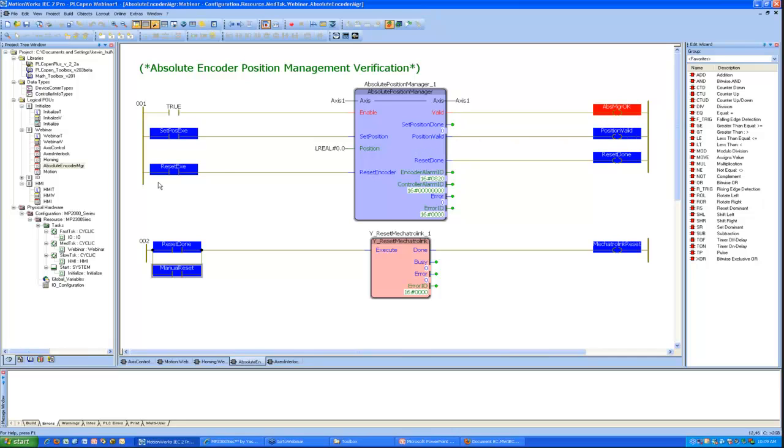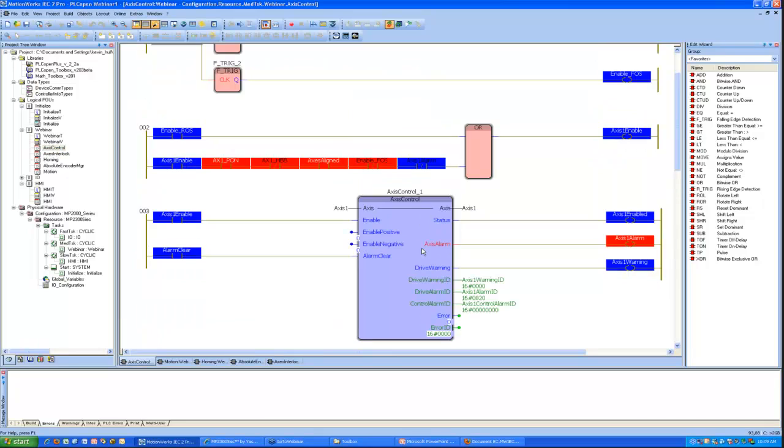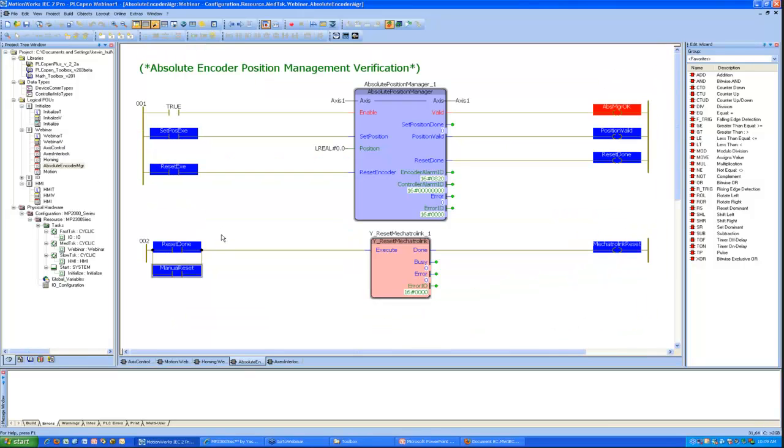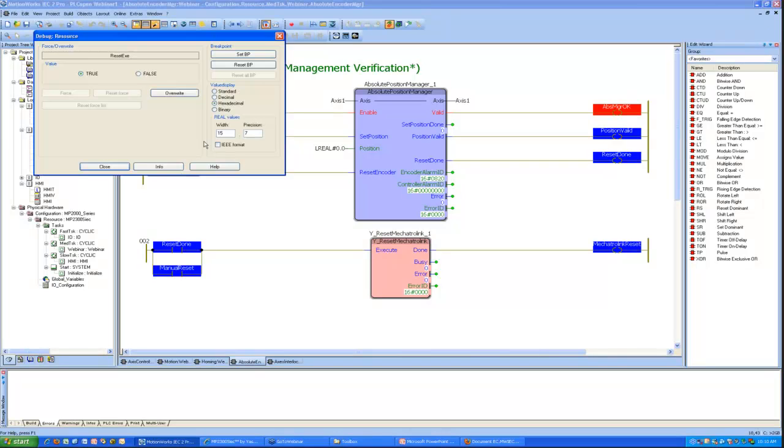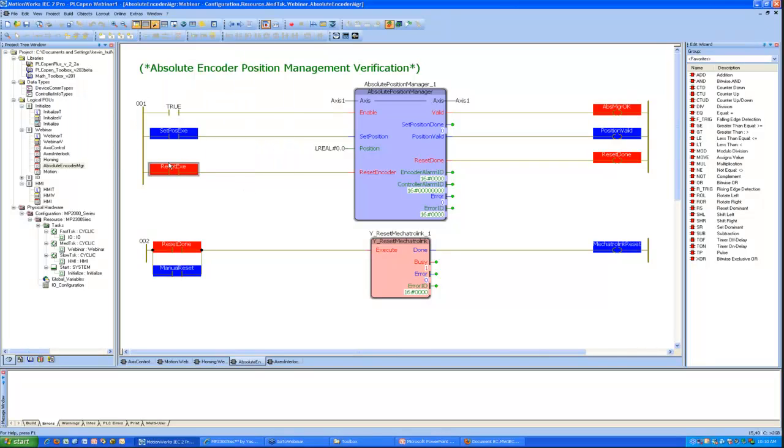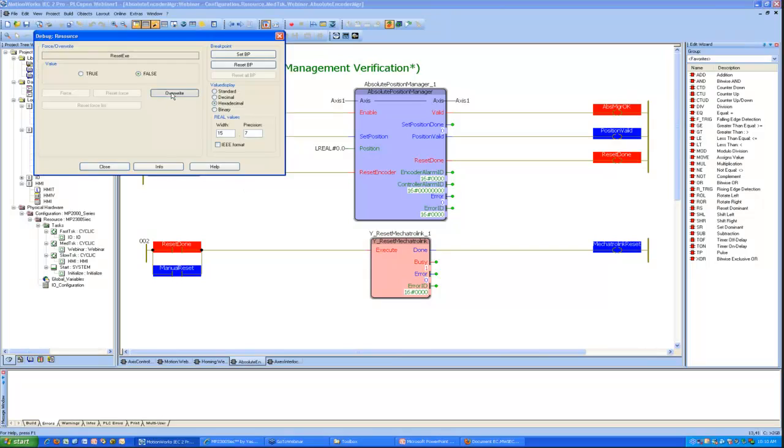It did disappear. And now that the amplifier has reset or restarted, we've lost our position valid output. And that is because now the amplifier is displaying an encoder related alarm. So I have an axis alarm. It says A82. And that's what the amplifier is showing on its front panel right now. So I'm using this output again in some interlocks to enable the servo or to actually move the servo in an automatic mode. So now we're prevented from doing that until we resolve the situation with the absolute encoder.